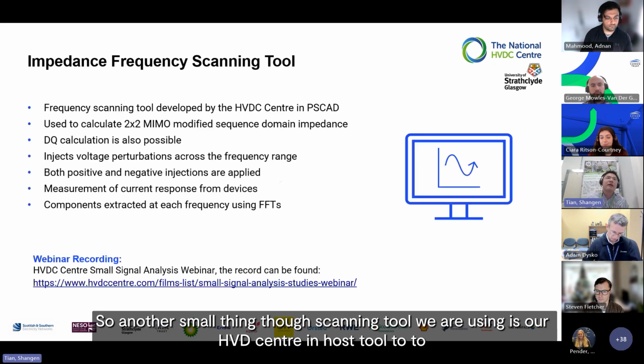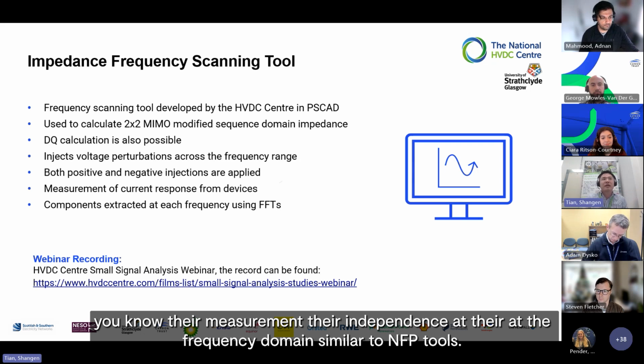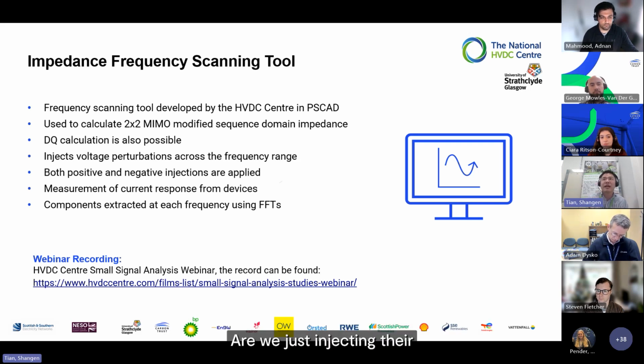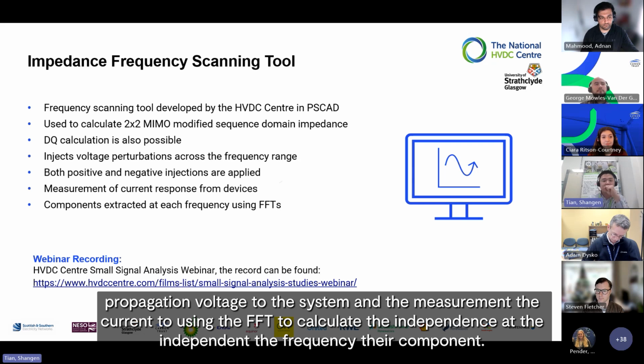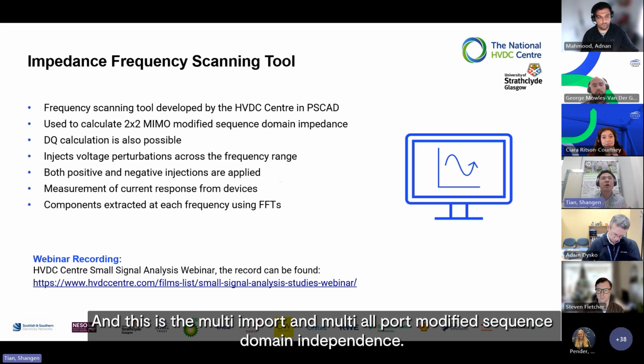Another small signal scanning tool we use is our HVDC Center in-house tool for measuring impedance in the frequency domain. Similar to the NFP tool, we inject a perturbation voltage into the system and measure the current using FFT to calculate the impedance at each independent frequency component—this is the multi-input, multi-output modified sequence domain impedance.